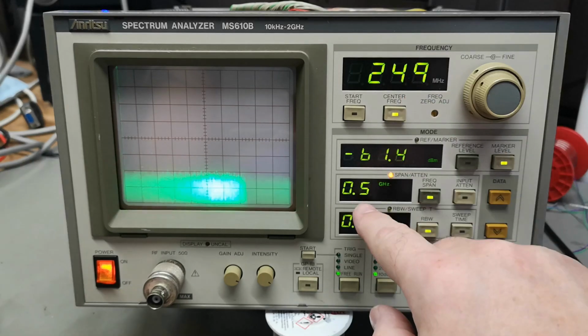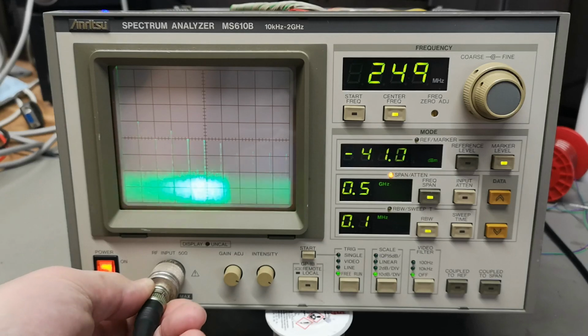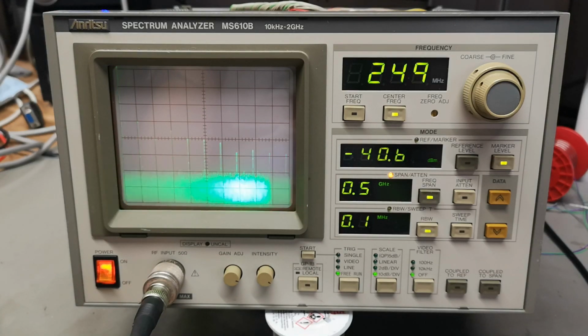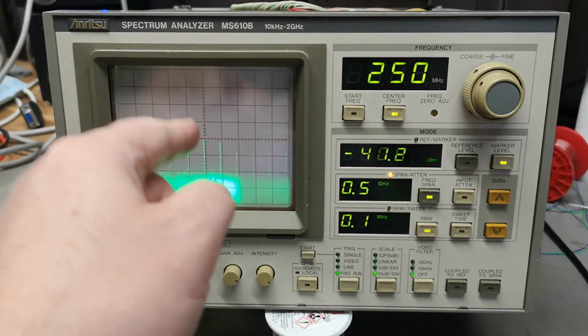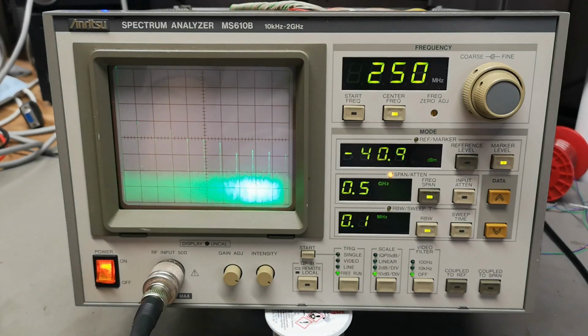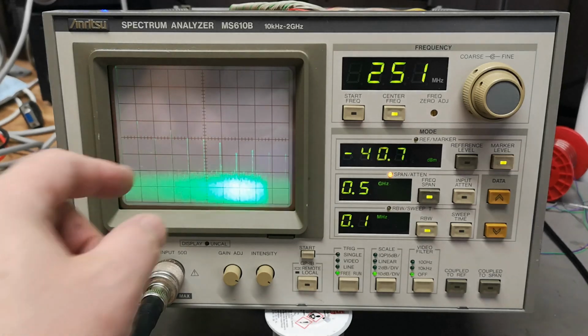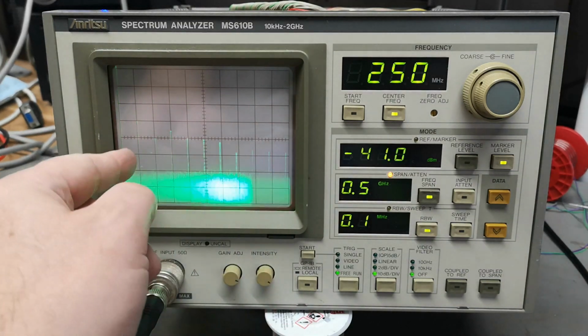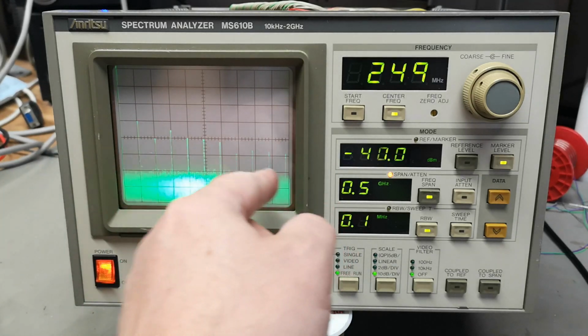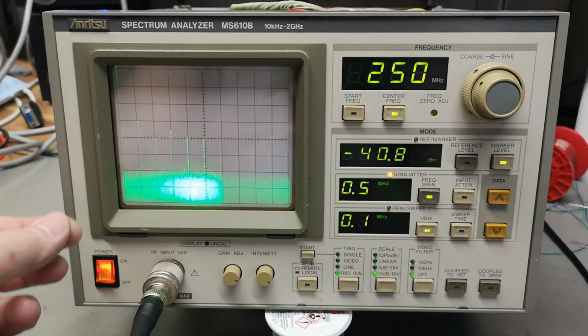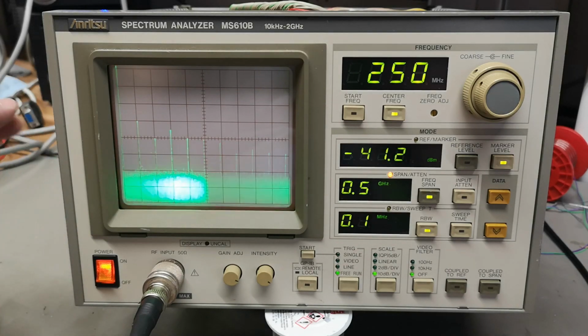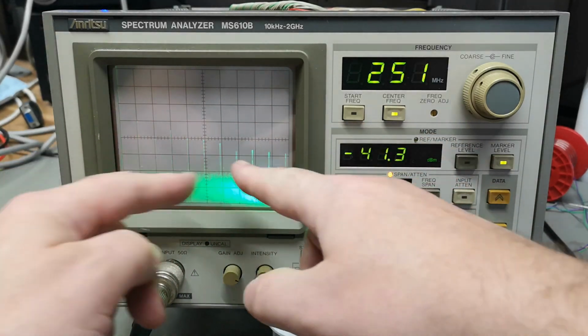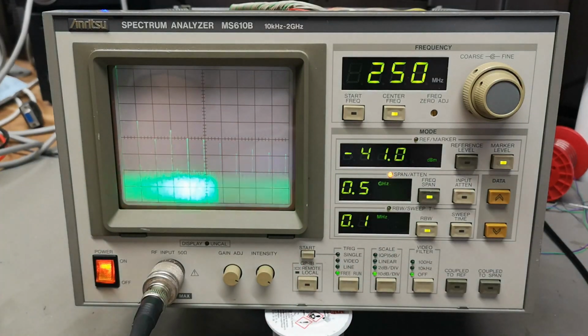center is 250 and my span is 500. See? That is a lot of harmonics, exactly as I want, because I actually want this to be able to calibrate for correct frequency. And since this is 50 megahertz, that means it should be 50 megahertz per division here. And all I have to do now is stick in my little adjustment for horizontal, the width, and then make the picture a little bit wider, so I can actually calibrate this readout here so it's accurate. And that is definitely how you do this, because it's analog.